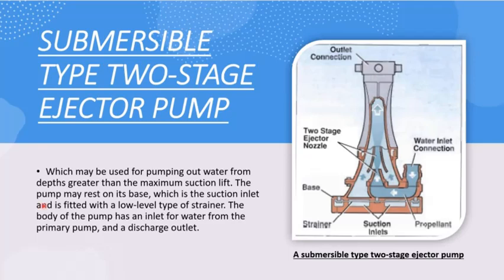The next type is the submersible ejector pump, which is used in cases where you have to pump out water from depths greater than the normal suction lift. In such cases you cannot use normal pumps, so the pump is submerged in the fluid to be pumped out. Water is introduced through the water inlet connection as the propellant. At the converging section, due to the Venturi effect, the pressure is reduced and the surrounding fluid gets sucked into the propellant stream and carried out. Since this is a two-stage pump, there are two ejector nozzles.